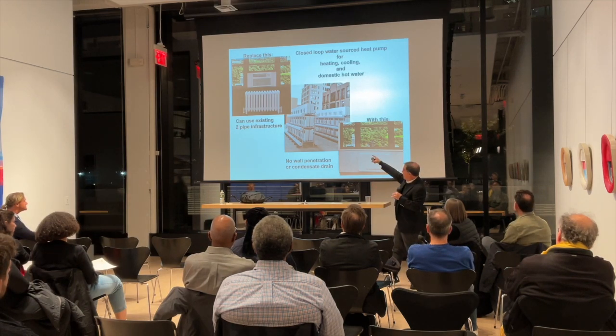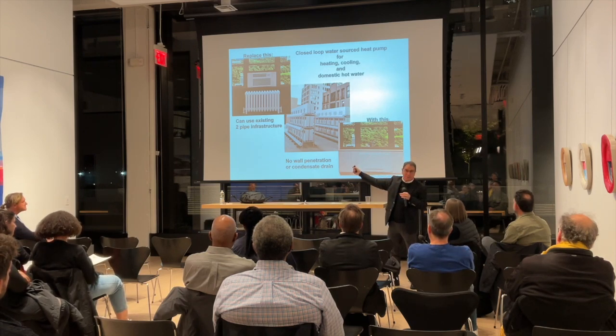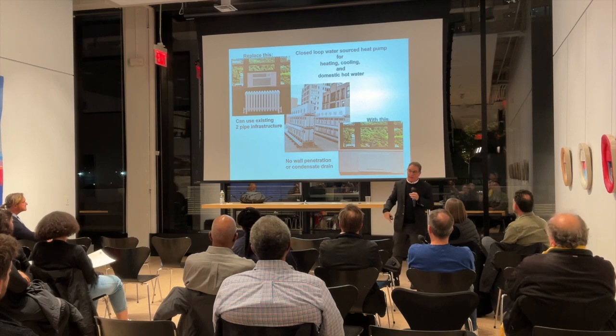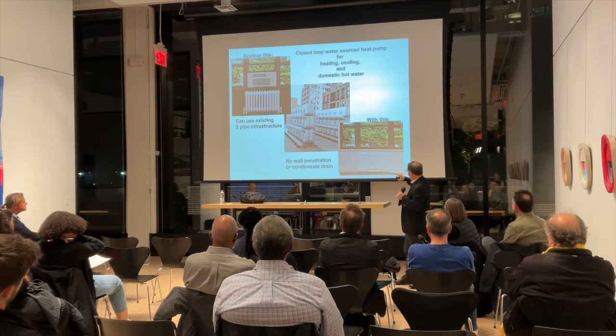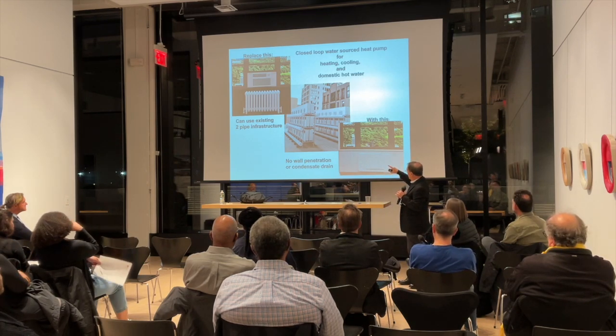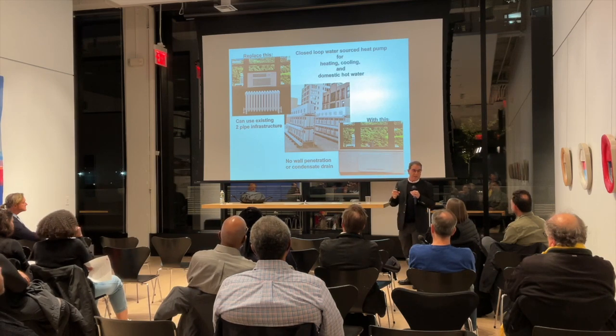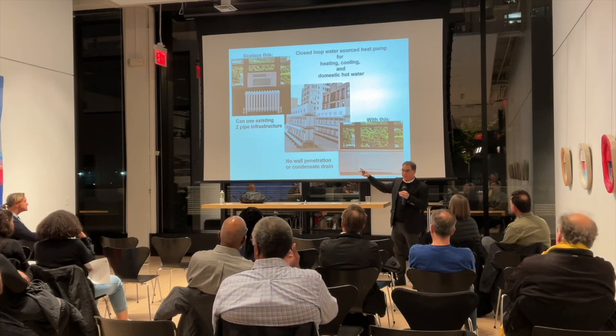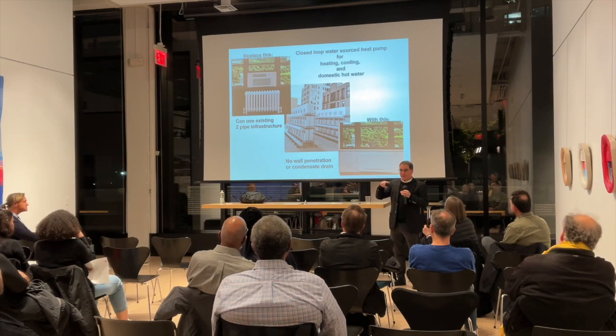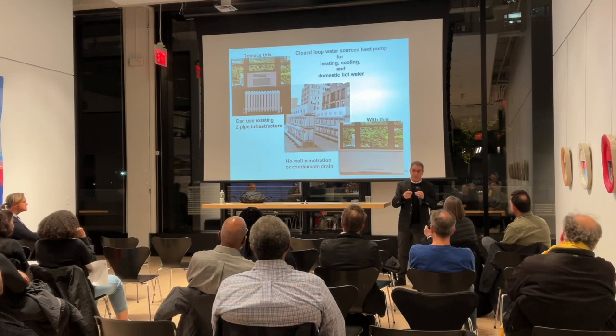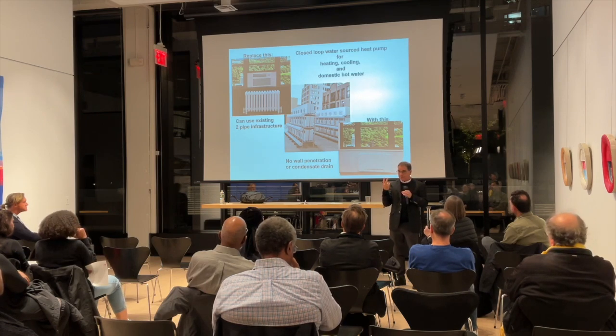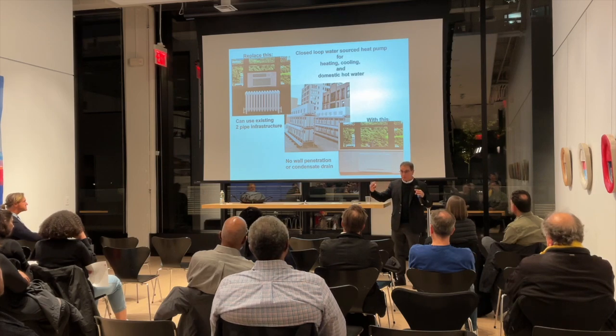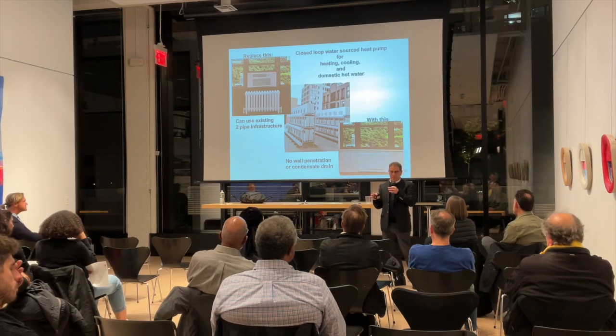What you have is an air conditioner in the window, a radiator that's got steam or water in it, and a boiler downstairs. And instead of that, you get this. What's in the middle is an array of heat pumps, but they're water source heat pumps. They are producing 70-degree water into a 2-pipe system. So if you're renovating a building that has a 2-pipe system, this could be a very good solution. There are logistic issues to be able to do that.